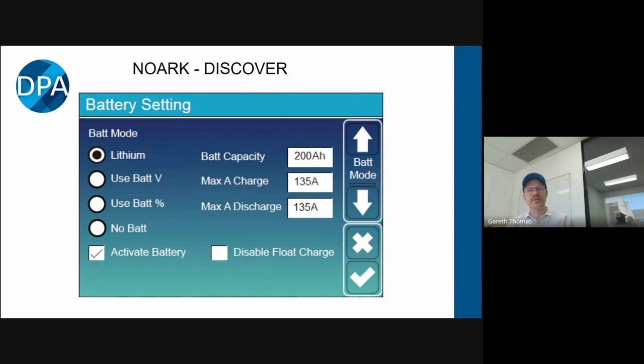So if the battery is broadcasting a maximum of 200 amps charge, and you put 135 in, it will only charge it at 135. But if the battery is saying only give me 100 amps, it won't charge it at 135.